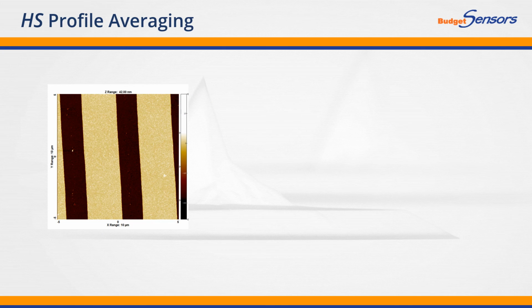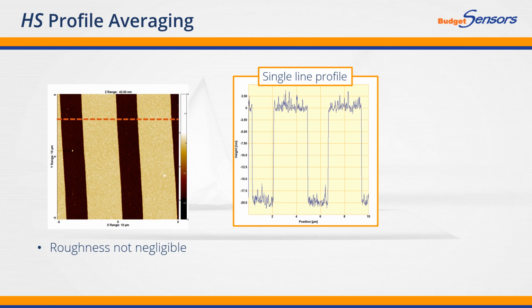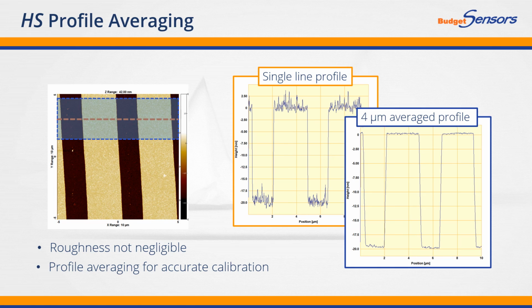Please note that the roughness of the HS surface is not negligible relative to the total step height. Calibrating your AFM system based on a single profile line can lead to a large error. This is why we recommend that a profile is averaged over several micrometers for accurate calibration.